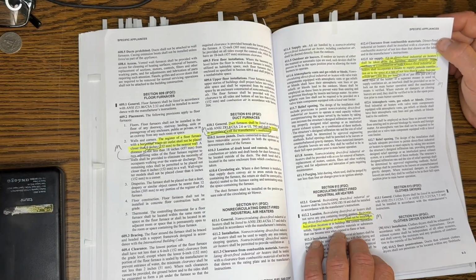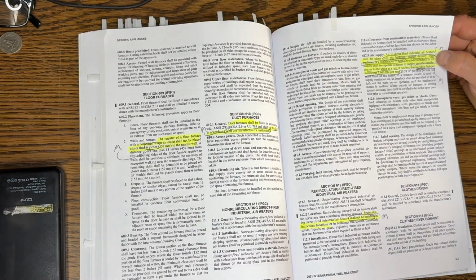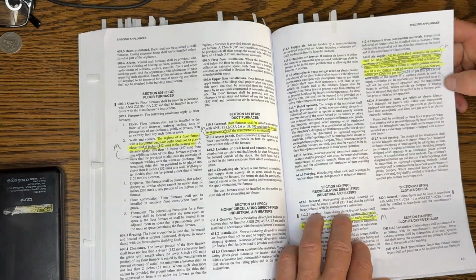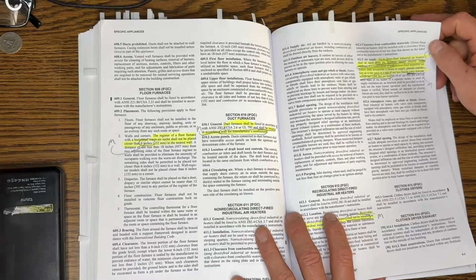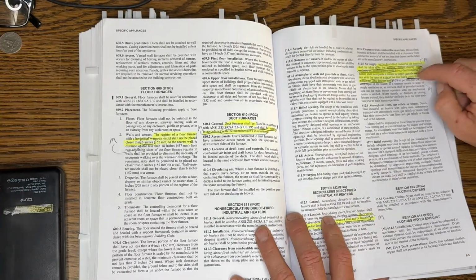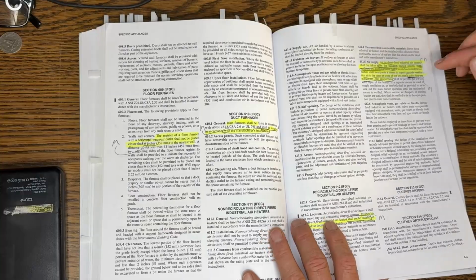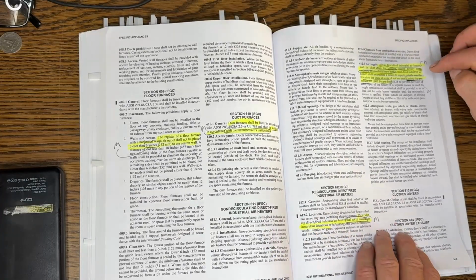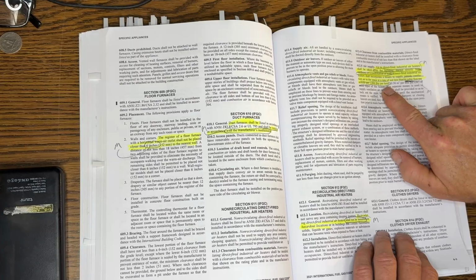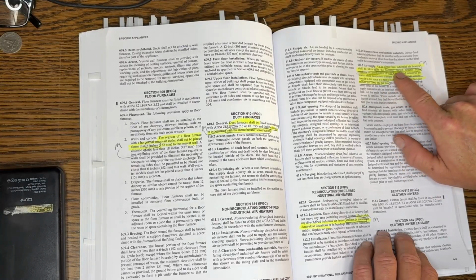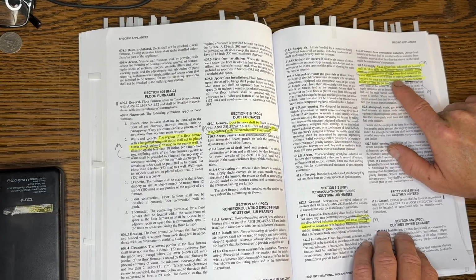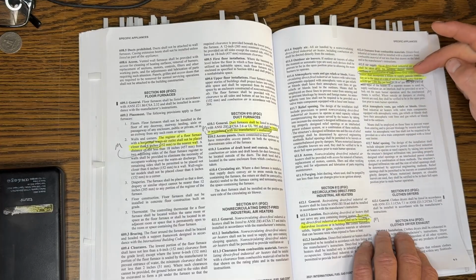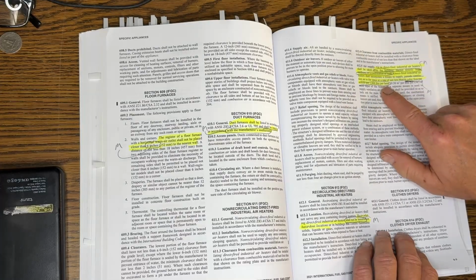Okay, what do you got here? Air supply. I had 2 questions out of this one. And just because I have an M and 2 questions, I probably had multiple references I had to look at. I just don't remember. But keep in mind, you can answer a question just by knowing this air supply section. So magic numbers, ICC loves magic numbers, 4 cubic feet per minute per 1,000 BTU. Air to direct fired industrial air heaters shall be taken from the building, duct to direct fired industrial heaters shall incorporate a means to supply outside ventilation to air in the space at a rate of not less than 4 cubic feet per minute per 1,000 BTU.